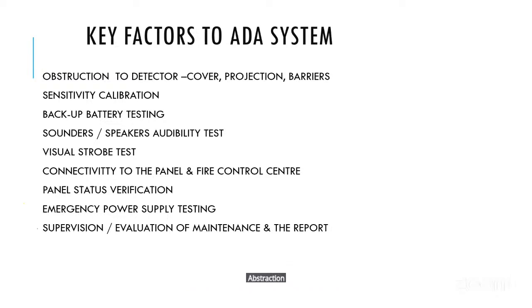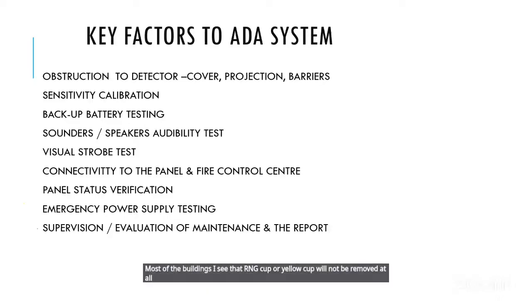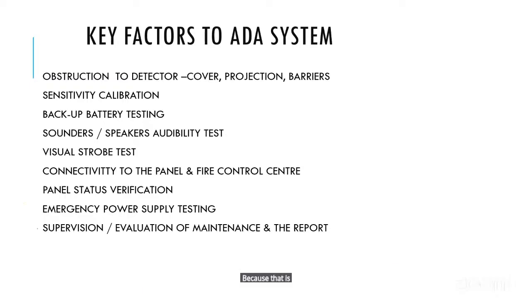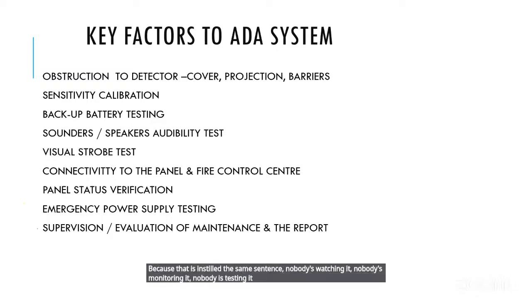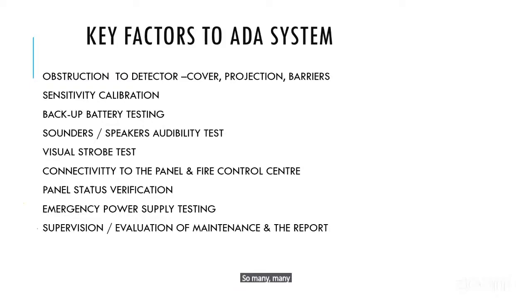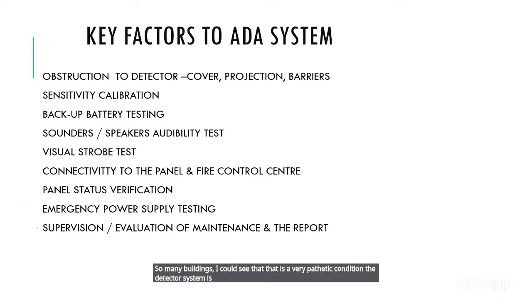Obstruction to detector. In most of the buildings I see, the orange cup or yellow cup is not removed at all. The plastic cover covers the detector because it was installed that way. Nobody is watching it, monitoring it, or testing it. That is why the detector's cover was not removed. In so many buildings I could see this very pathetic condition. The detector system is there, but obstruction of detectors by the cover, or any projection, will obstruct the flow of smoke and heat. So that must be identified.